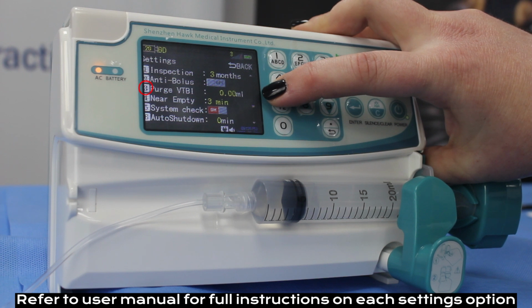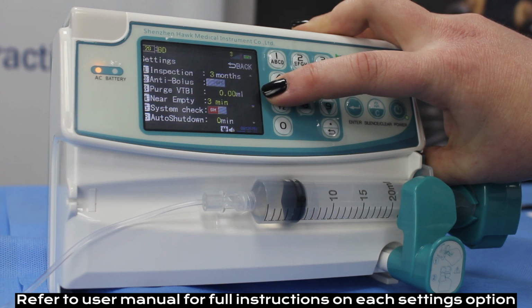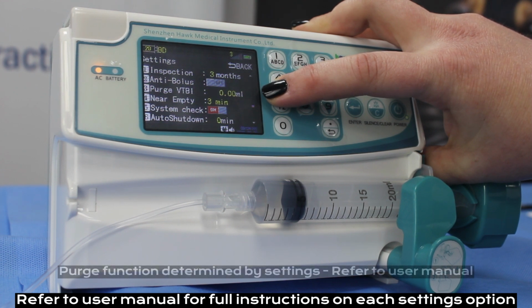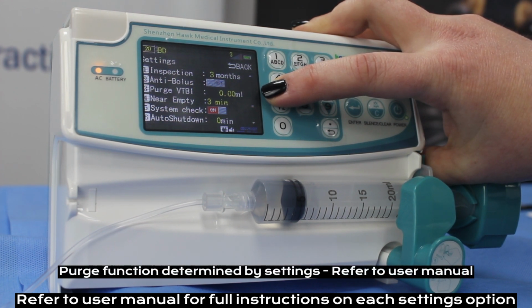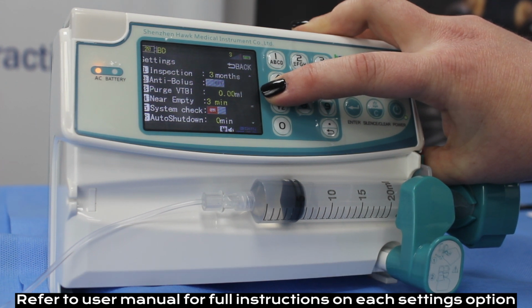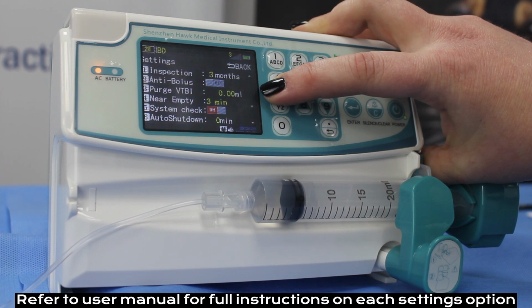Your purge volume to be infused rate is a setting that can be used while in the stop screen of running your infusion. This will purge the line until it's clear of any bubbles, and it's very important that this isn't connected to your patient while you're doing this. Your pump should alarm if it detects connection to your patient and not allow you to do the purge volume to be infused.